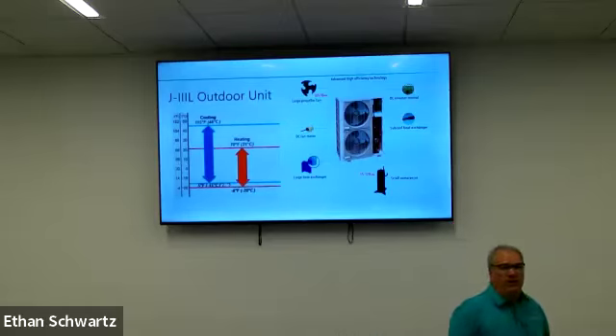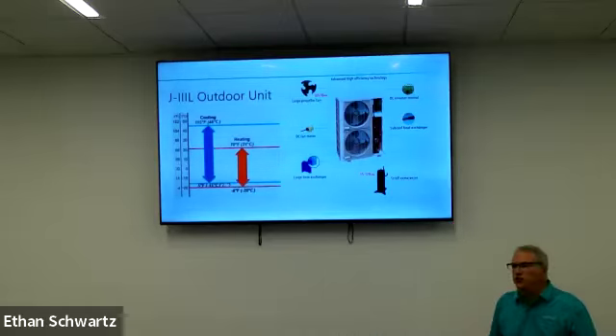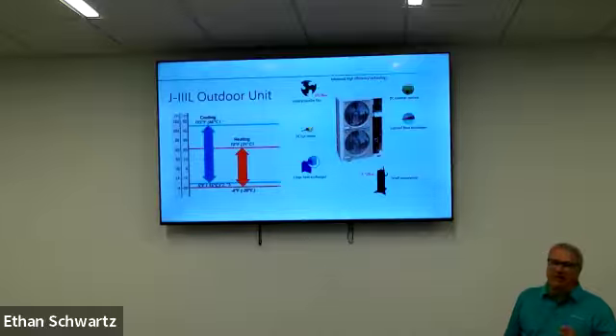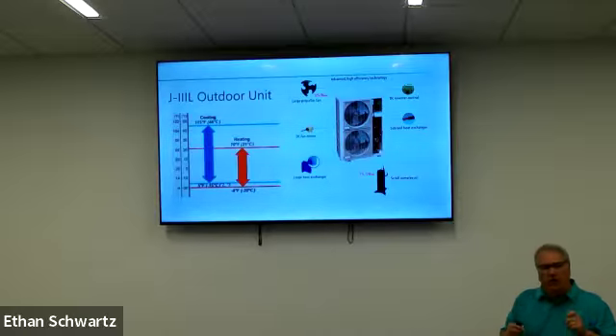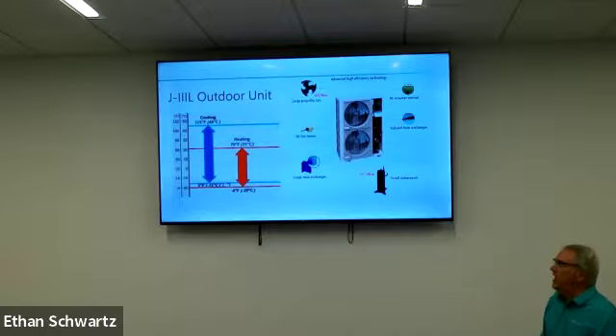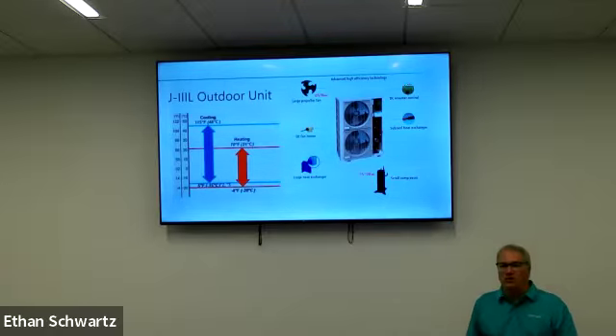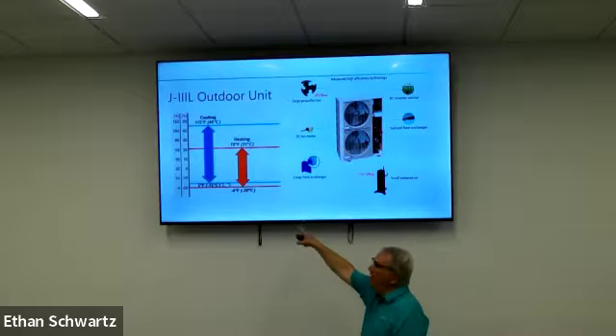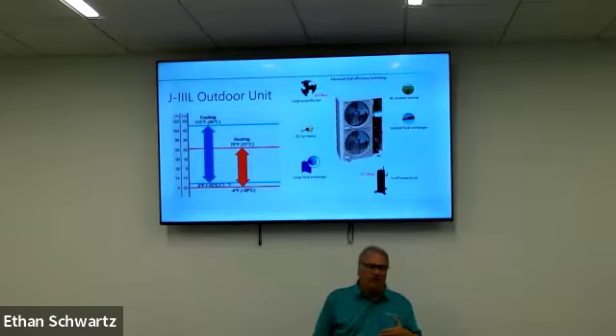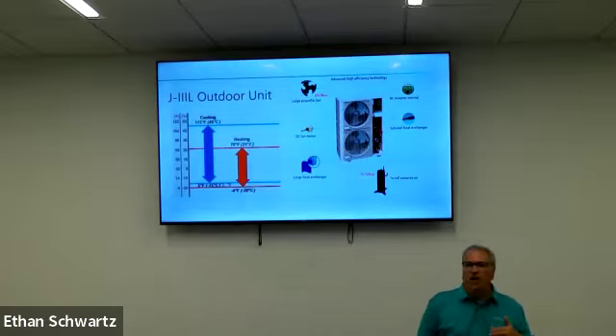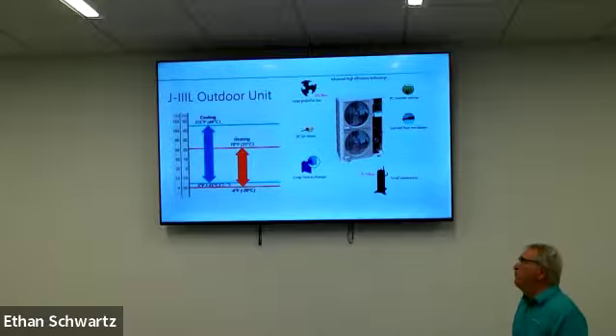So if you think you're going to be lower than that, you may have to go to the VU5, which is rated to -15 Fahrenheit. Let me say this about anything Fujitsu. There are no low ambient heating cutoffs, or cut off and restart in heating mode. They are going to run and will continue to run unless some other protection kicks in. But they will always continue to run. It's just how we rate and test this. Fujitsu is very conservative in their representation of their numbers, and they always perform better.